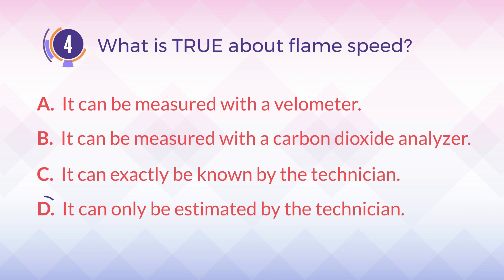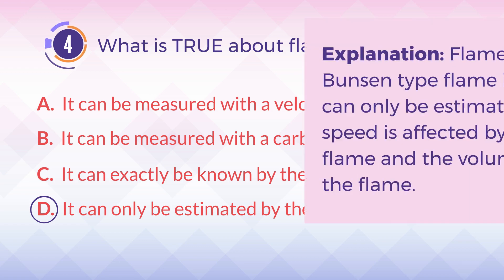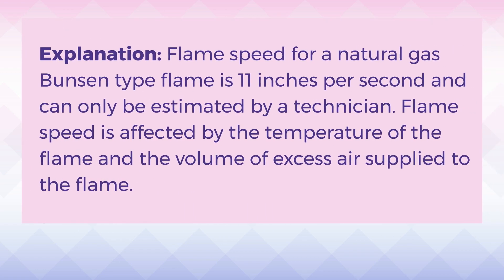The answer is D: it can only be estimated by the technician. Flame speed for a natural gas Bunsen-type flame is 11 inches per second and can only be estimated by a technician. Flame speed is affected by the temperature of the flame and the volume of excess air supplied to the flame.